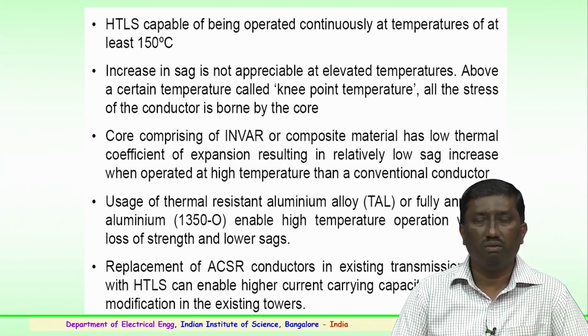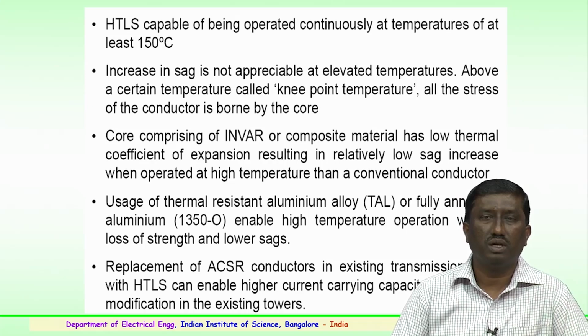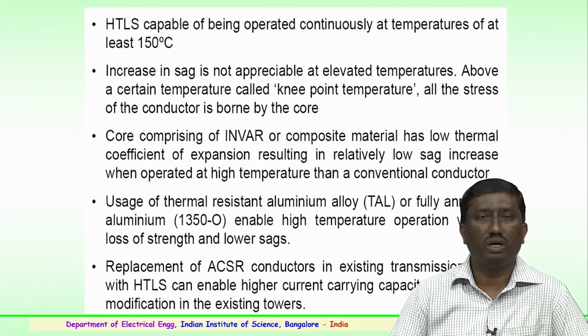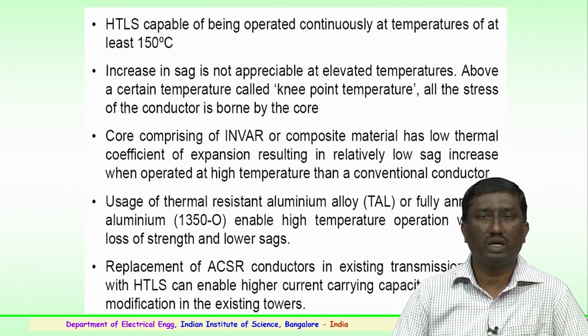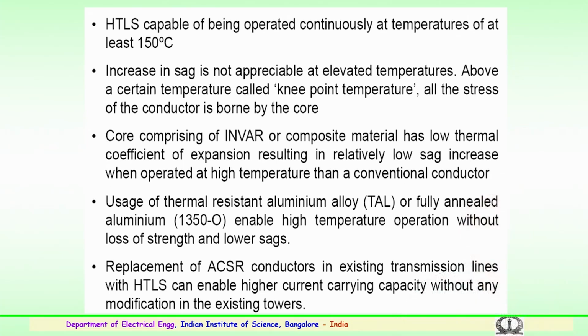This results in relatively low sag, because the operation of this conductor at a very high temperature, because of its inherent properties of having a low thermal coefficient, will result in a low sag or no sag when operated at higher temperature than the conventional ACSR or AAAC conductors. Here the usage of thermal resistant alloy, that is thermal resistant alloy or fully annealed aluminum 1350-O, enables high temperature operation without loss of strength and reduces the sag.